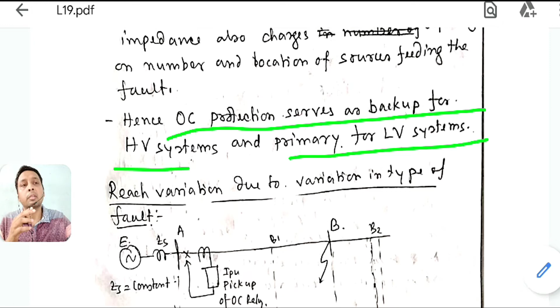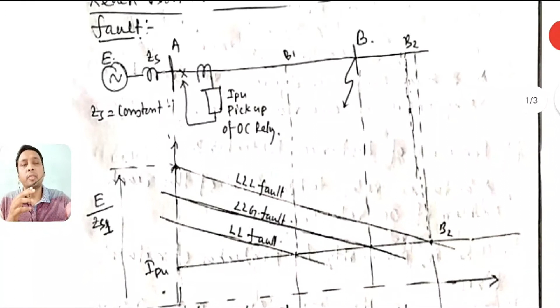So how does the reach vary? The first reason is the change in the type of fault. Suppose I have taken a simple feeder, with just one generator source, and this is the bus A and this is the line B. Suppose I want to protect only this portion. My reach should be from here to here. The relay should sense any fault between these two. So what should my setting be? I should put some IPU, that is the threshold value.